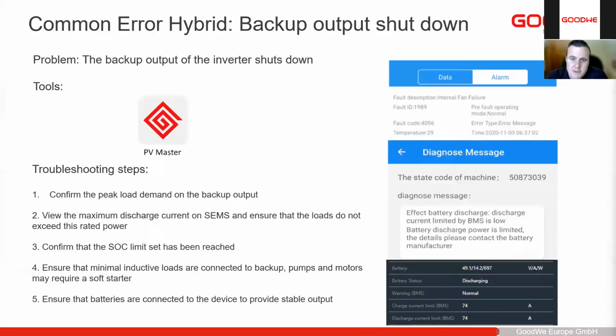Next, we'll go through the common errors that we experience on the hybrids. So the most common error that we'll get is backup output shut down. The backup output can shut down for multiple different reasons, especially because we are limited to the inverter capacity on the backup. We need to confirm the peak load demand on the backup output to see whether there's been any problems.